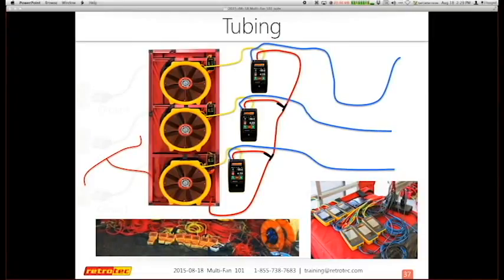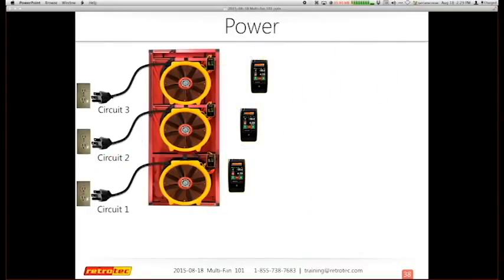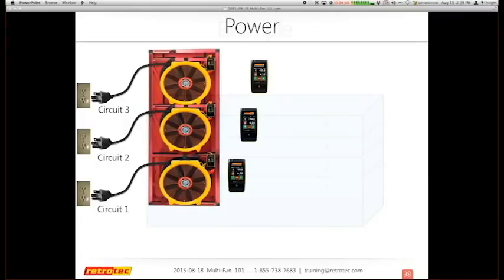One important point about power: if you're going to have three fans — even two fans — you really need a single circuit for each fan. If you put two fans on one circuit there's a high probability you could blow that circuit. Always assess your power and make sure they're on individual circuits.